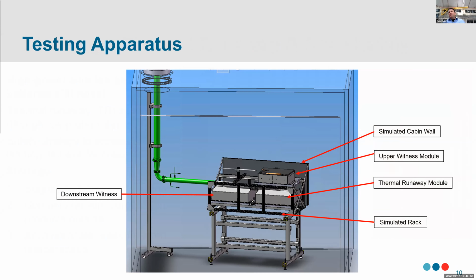So again, we benefited from other labs, and in order to determine if thermal runaway could be contained, we set up a test rig with actual battery modules inside their containment enclosures. Then we caused one module to go into thermal runaway with witness modules sitting one beside and one above, in the proximity they would be in the back of the aircraft for worst case locations.